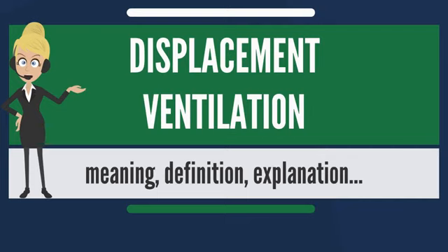Diffuser types vary by application. Diffusers can be wall-mounted, located against a wall, corner-mounted, at the corner of a room, or freestanding, above the floor but not against a wall. The cool air accelerates because of the buoyancy force, spreads in a thin layer over the floor, reaching a relatively high velocity before rising due to heat exchange with heat sources, for example, occupants, computers, and lights.